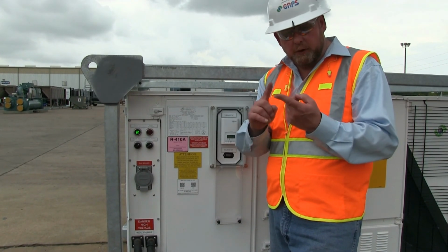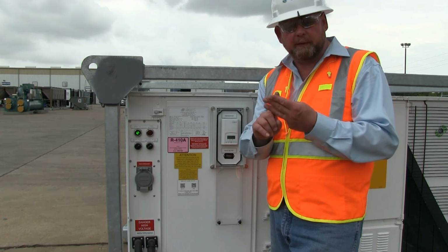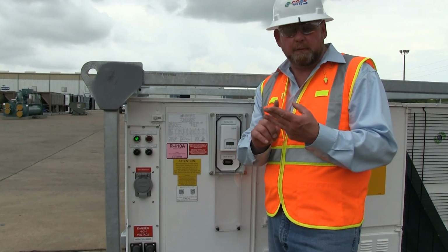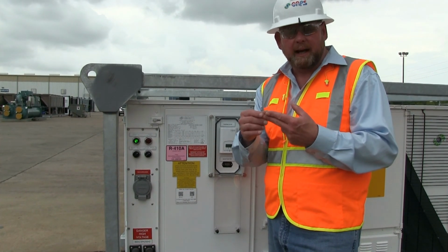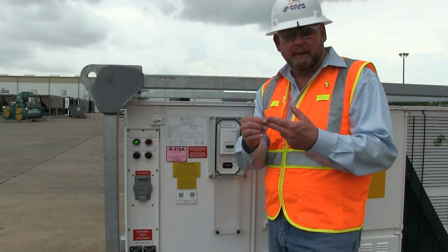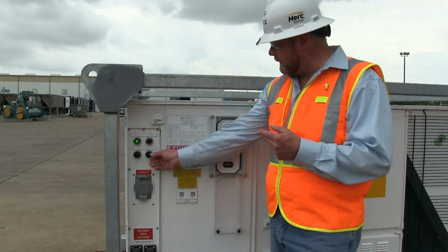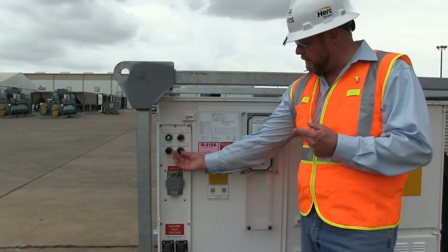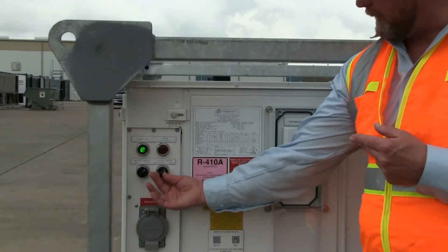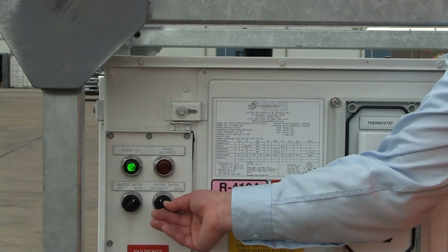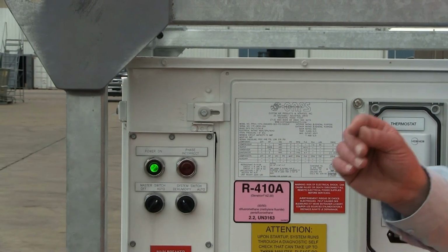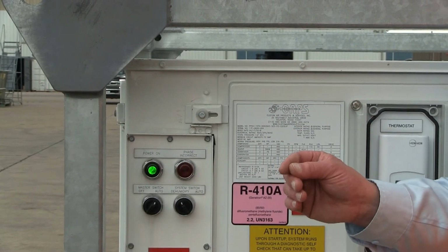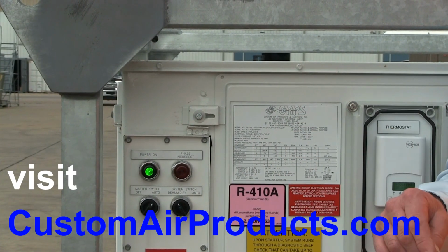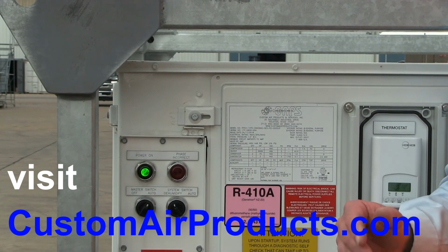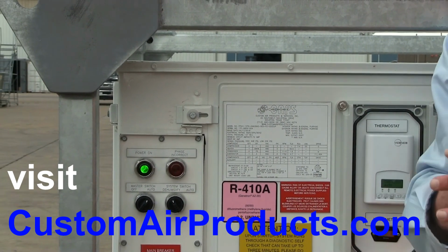We had mentioned it can do cooling, heating, and dehumidification. We accomplished the dehumidification by running the heating and cooling at the same time. And that's simply done by coming here to this system switch here, and where it says auto and dehumidify, you click it over to dehumidify, and that runs the cooling and heating at the same time, producing neutral temperature but dry air for restoration or dehumidification projects.